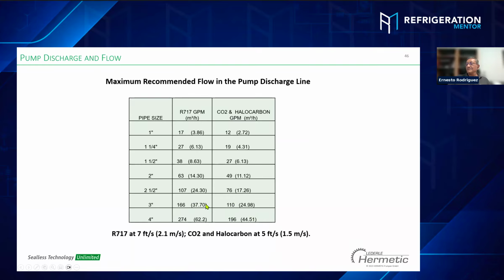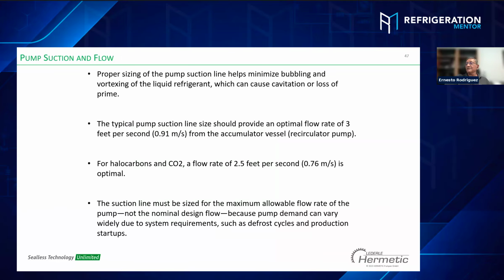If you undersize this pipe, you're going to have problems with the pump. Okay, the pump gives no increase in pressure. The pump is not making any noises. You need to be careful. Technicians need to be sure of the diameter on the pump's discharge, and of how the piping is. It's a very common problem. Many situations happen when the pump fails. I say, well, check the diameter on the suction and discharge of the pump, and they say, okay, it's too short, or it's correct. Okay.